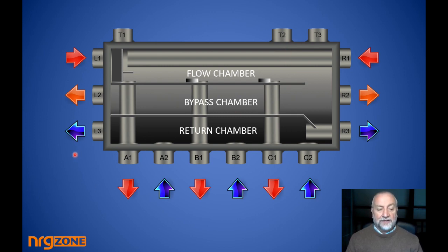The L3 and R3 are connected directly to the bottom chamber. I'm going to qualify what I said again. So is A2, B2 and C2. So you can also use those for returns if you want. Any return can be interchanged with any zone. So I could have, well, let's talk with the bottom connections. A1 and A2 form a logical circuit. Pump maybe on the flow, a non-return valve on the return, and you're off. We'll talk about the non-return valves again in a while.